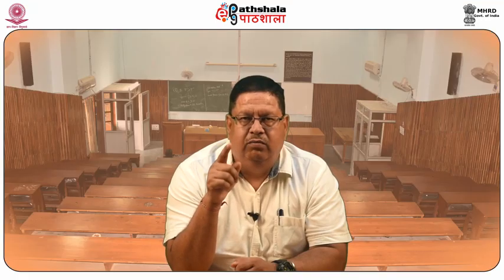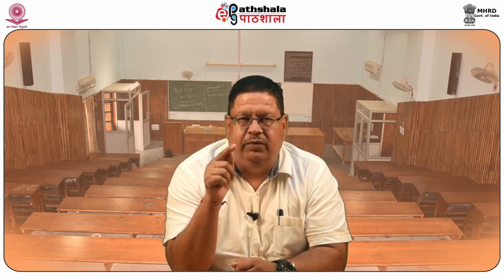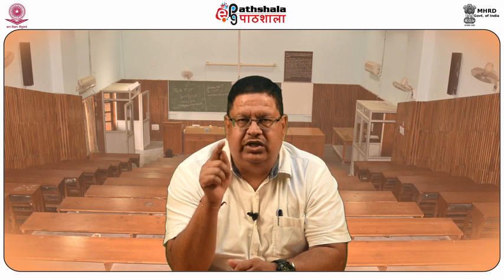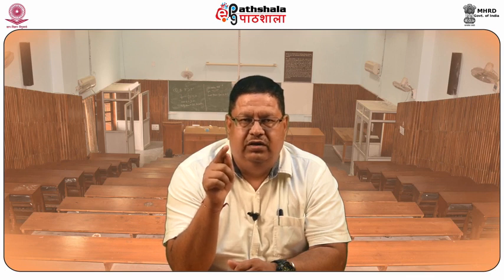Radiation detectors, modes of working. The rise time: the time taken for the preamplifier output voltage to reach its maximum value is called the rise time. The rise time of the detector is determined by the charge collection time of the detector and is not affected by the value of the components of the circuit. The decay time of pulses is determined by R and C.